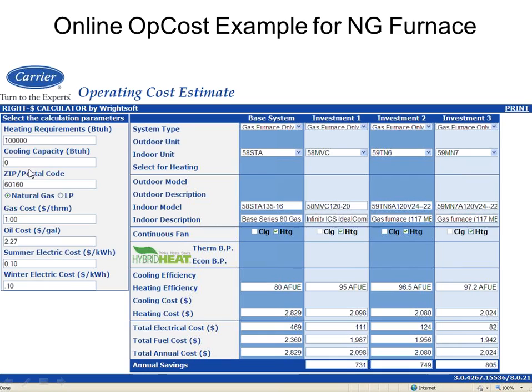And for this size house, at this zip code with these fuel costs, it's telling me that I spend about $2,800 a year on my gas heating operation. And then of that, $469 is electric to run my fan, and $2,400 is my gas cost. If that doesn't match up with what your customer's spending, you can come over here and tweak your gas rate to make it match.